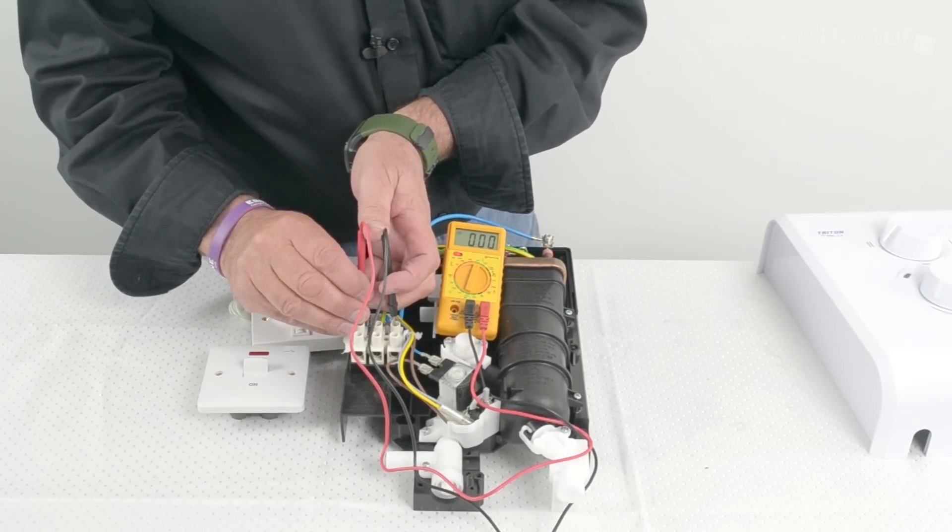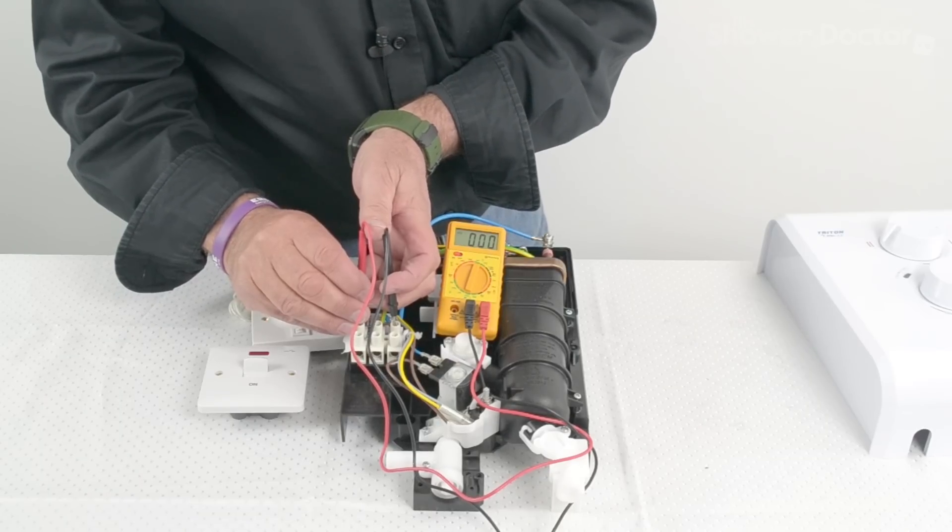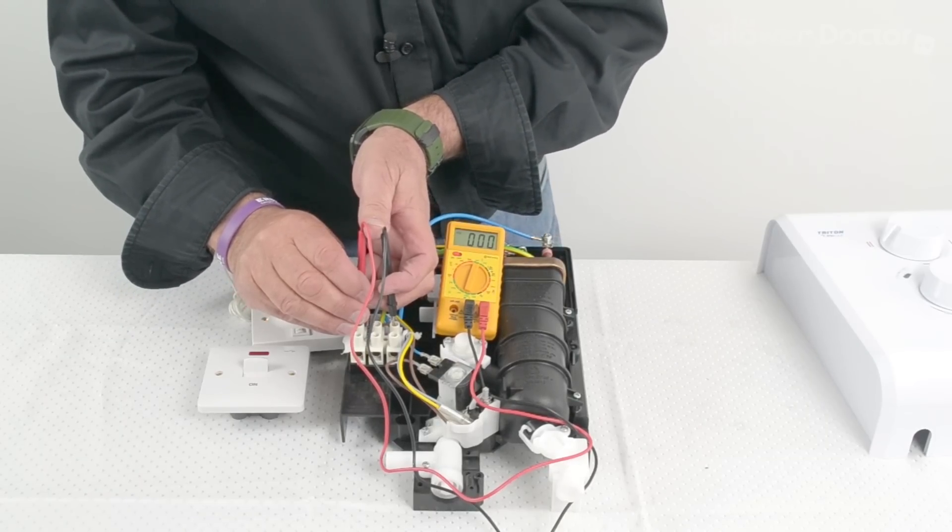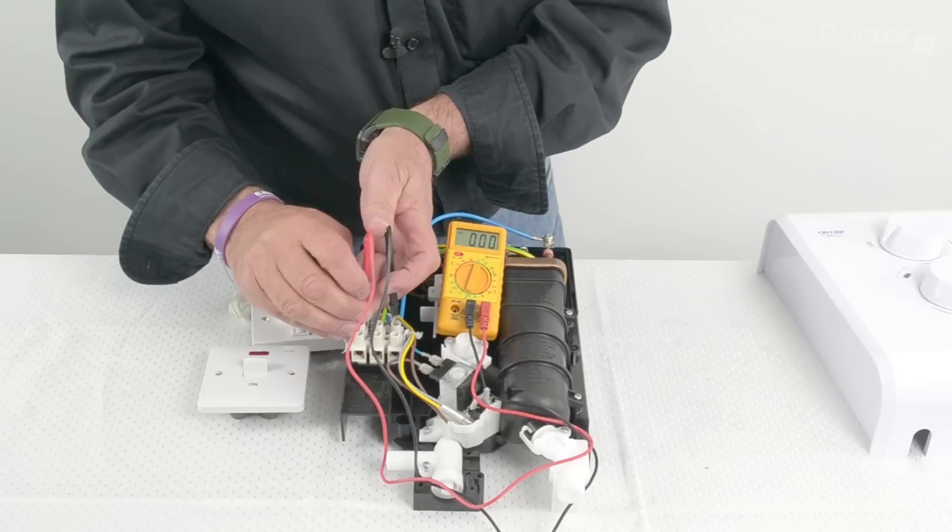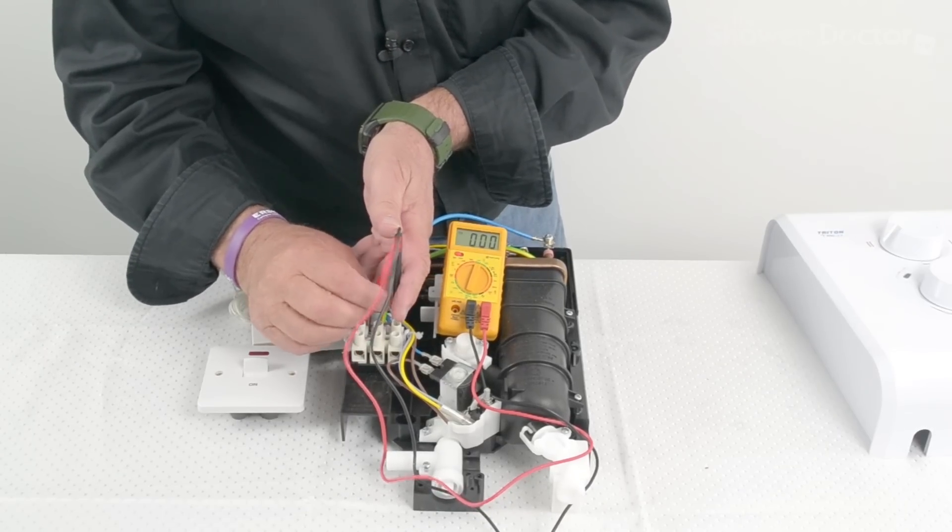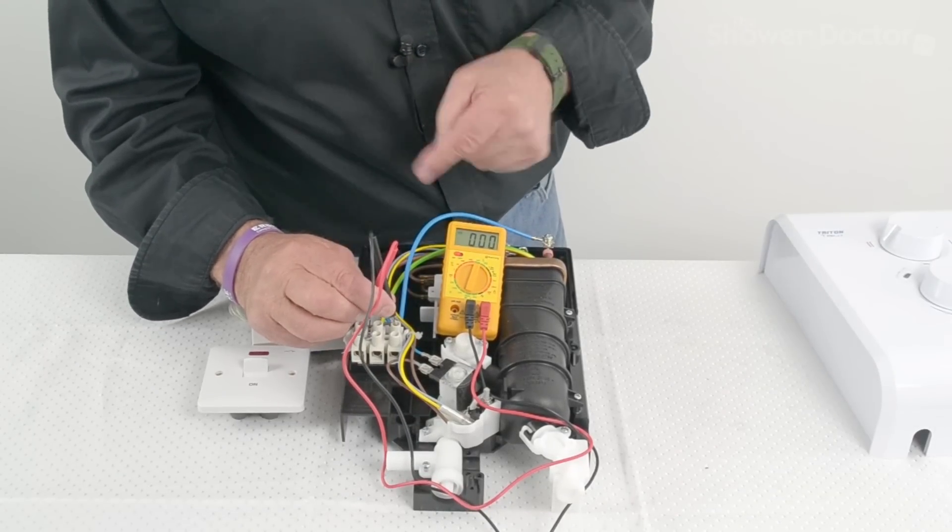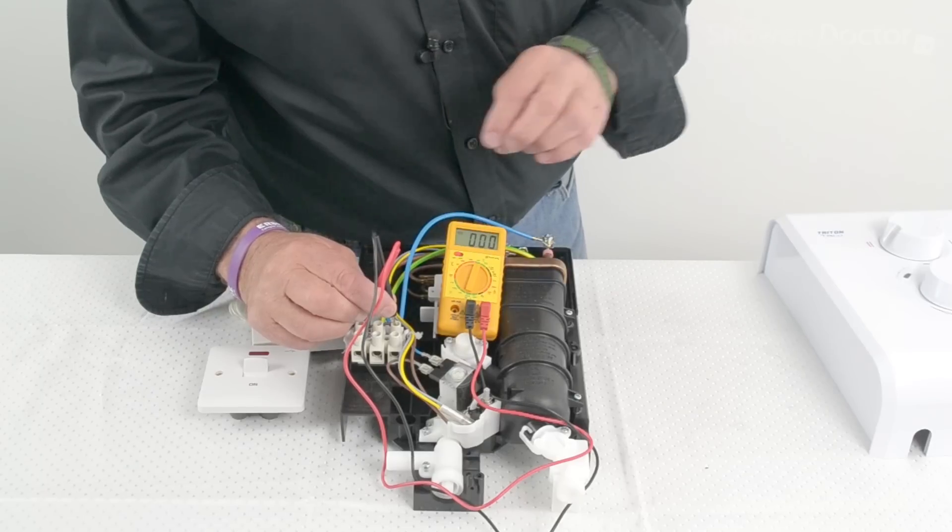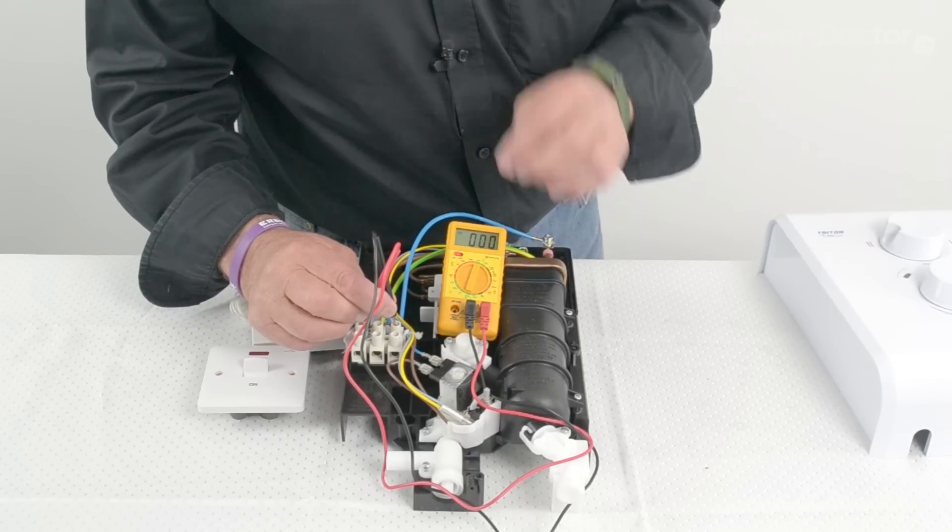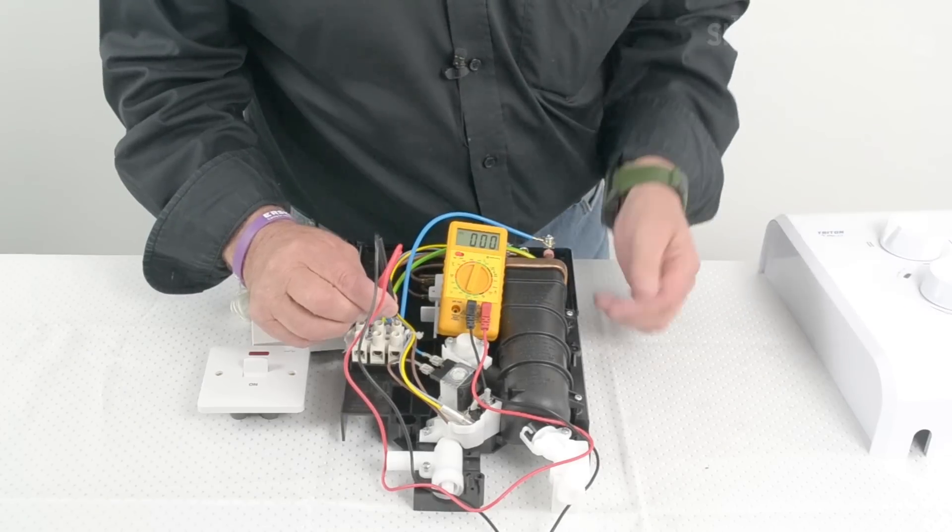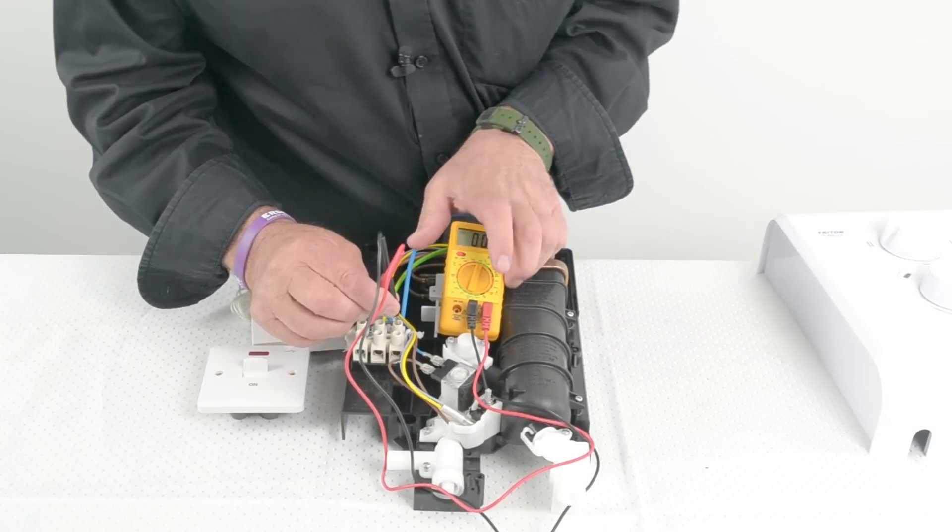Now as long as you've got power reading here that proves that there's power coming into the unit and so therefore because that's live the rest of the unit should work and we carry out the other tests after that. But we now know that this has power so we now go back and switch the isolating switches off.